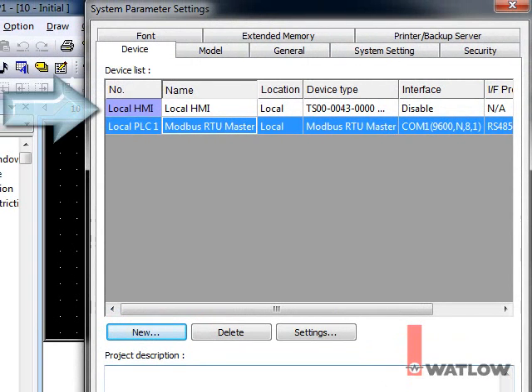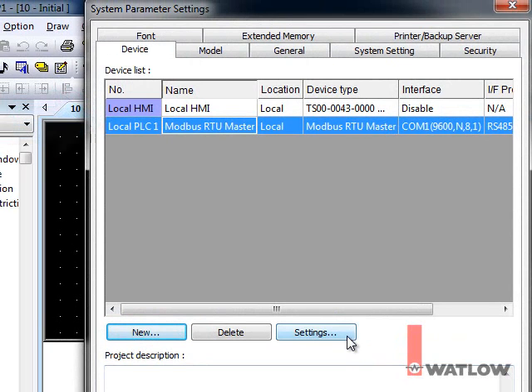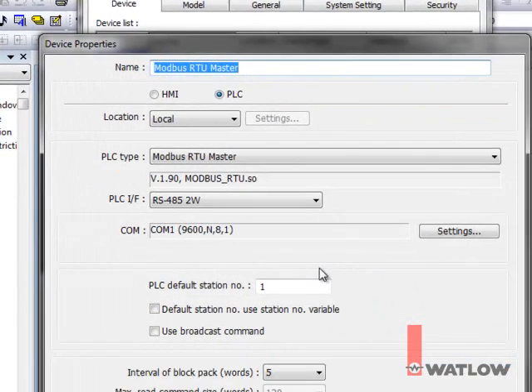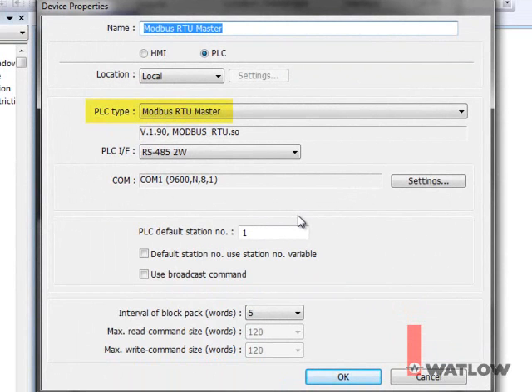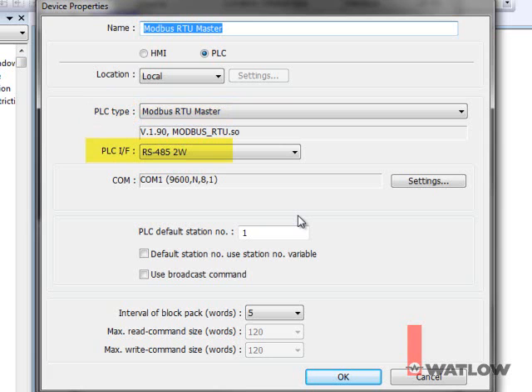The new project has two devices, the OIT called Local HMI, and a Modbus RTU Master. Let's configure the Modbus RTU Master device by selecting it and clicking Settings. The Modbus RTU Master communications driver is selected for PLC type. EasyBuilder 5000 refers to any device OITs communicate with as a PLC because that's a common type of device used with them. For PLC interface, select RS-485 2W to configure the driver for a two-wire 485 connection to the RM controllers.